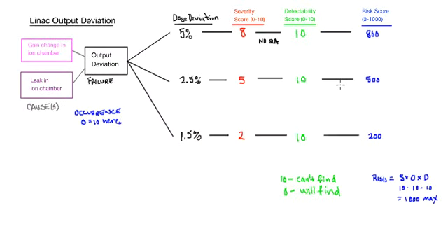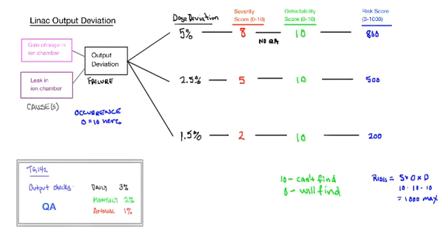So coming back to our example, let's see what that would look like if QA was performed as recommended in TG 142. We'll start with the daily QA. Now remember the sensitivity of that test, so it can only find things that are 3% deviation. So it won't find this one, it won't find that one, but it will find this one.